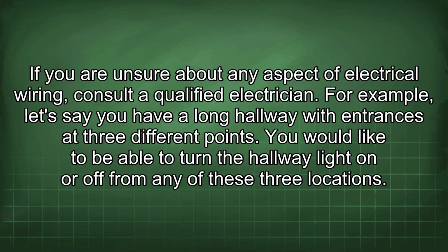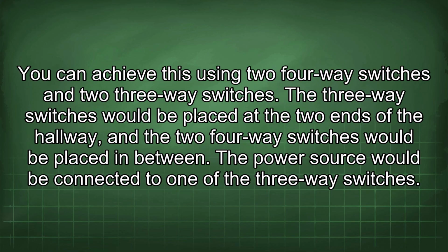For example, let's say you have a long hallway with entrances at 3 different points. You would like to be able to turn the hallway light on or off from any of these 3 locations. You can achieve this using 2 4-way switches and 2 3-way switches. The 3-way switches would be placed at the 2 ends of the hallway, and the 2 4-way switches would be placed in between. The power source would be connected to one of the 3-way switches.